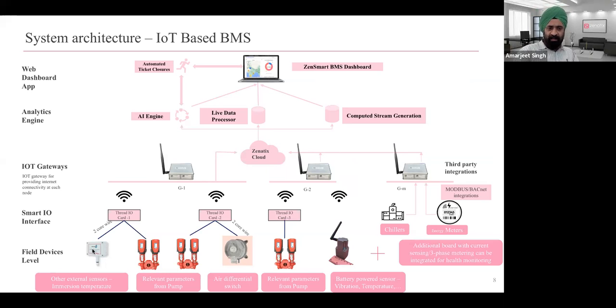At the lowest layer, you still have these field devices, similar to the field devices you'd get in a BMS. These are sensors or actuators talking over analog or digital inputs and outputs, 0 to 10 volts, 4 to 20 milliamps, etc.